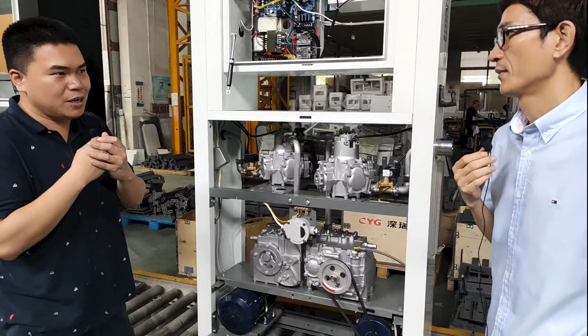Sometimes if it's broken, the motor isn't running and operation isn't good, but usually the capacitor is broken, not the motor itself. So sometimes you need to back up the capacitor for the motors if your station's power is not stable, which could damage the motor or cause the capacitor to go bad rather than the whole motor. So we just need to replace the capacitor to solve the problem. A mechanic needs to check carefully whether the motor, capacitor, or coil has gone bad, so we check it based on experience.